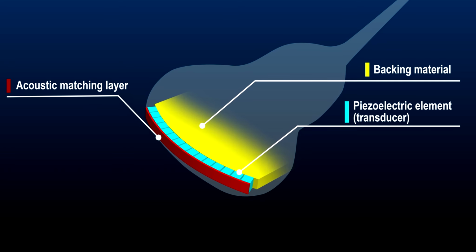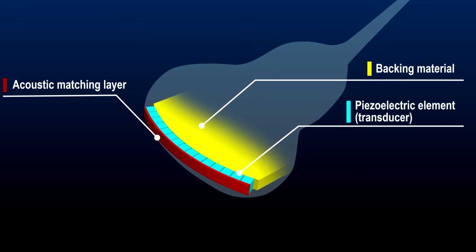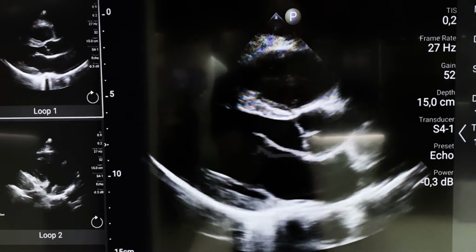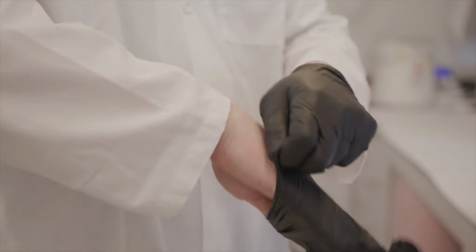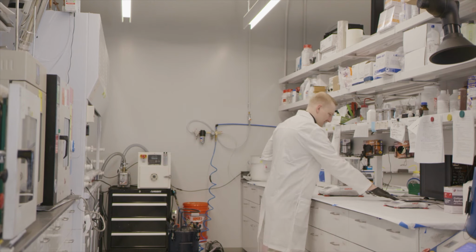Most of the wearable ultrasound devices developed thus far have been stretchable, resulting in improved wearability compared to traditional rigid probes. However, they have limitations such as a lack of an acoustic matching layer between the piezoelectric element and the skin. An acoustic matching layer is used in traditional ultrasound probes and is carefully designed to have an acoustic impedance that is intermediate between that of the piezoelectric element and the tissue being imaged, maximizing transmission of ultrasound waves into the body. However, existing matching layers are typically composed of rigid particles embedded in epoxy resins, which do not have the stretchability necessary for conforming to the skin and thus cannot be readily used in wearable ultrasound devices. To address this limitation, we have created a wearable ultrasound patch with a soft and stretchable, mechanically compatible matching layer.